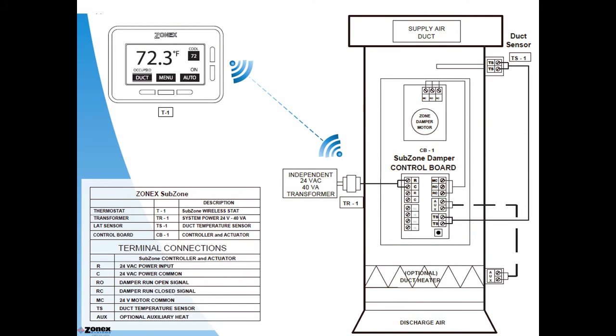As we said, subzone is a standalone or floating zone solution, controlling a fully modulating damper with the wireless programmable thermostat, and it provides excellent control and solves the problem when an area is too hot or overcooled. The subzone is designed to solve the problem of overconditioned areas. A 24-volt 40 VA transformer powers the subzone. The damper board, like the damper board on the Gen 3, supports auxiliary contacts to energize and control supplemental heat sources. Subzone is a great low-cost problem solver.